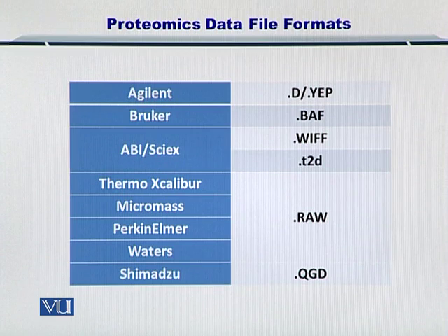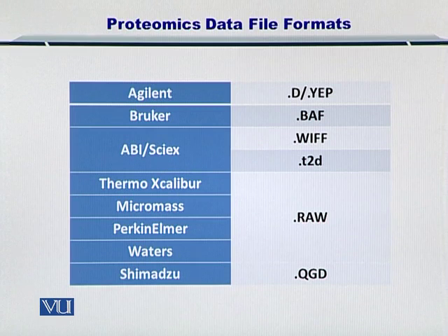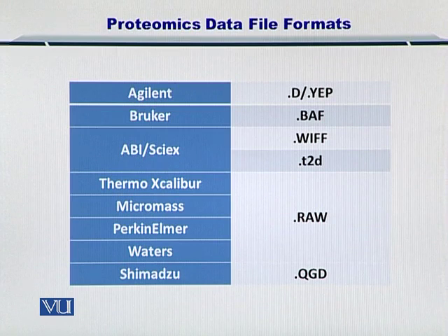Each company has its own format, as shown in this table. For instance, Agilent gives you a .d or .yep file, while Waters, Thermo Xcalibur, and others give you raw file formats. All of these formats are binary formats — you cannot read them yourself by opening them in any text editor. So two key points: each manufacturer has its own data file format, and these formats are binary, meaning you need to convert them into human-legible forms.